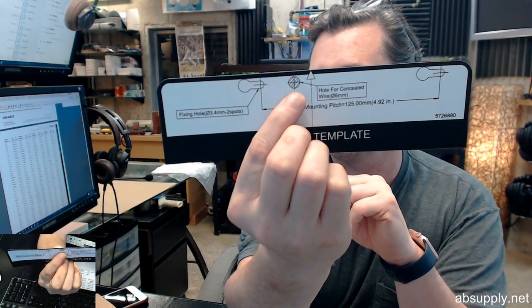Speaking of wire, step 2 on page 6 is going to be plug the AccuSensor 3 harness into the 4-pin connector on the AccuSensor 3. That's pretty simple and straightforward how that's going to work. That's your harness, square round, square round. That, of course, lines up, square round, square round. Connect the black and red wires. Connect the black and red power wires to a Class 2 transformer, or the brown and red 12-volt wires.